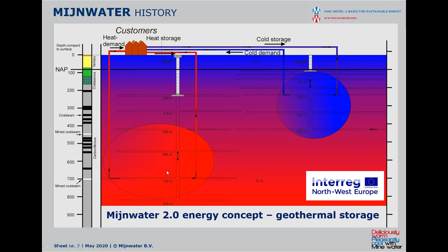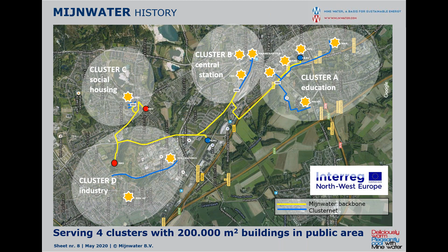Those wells are the 2 red dots in this picture, which are 2 hot wells, and the 2 blue dots, which are the cold wells. The return well is somewhere in between, but we didn't show it. Those wells are connected by a yellow line, the backbone, which carries the Mijnwater from the sources to the customers. The small white squares are basements, connecting this backbone to cluster grids. In the clusters, we don't have Mijnwater; the basements exchange energy from the backbone to the cluster grid. Right now we are serving 200,000 square meters in a public area, about 500 dwellings and commercial buildings.